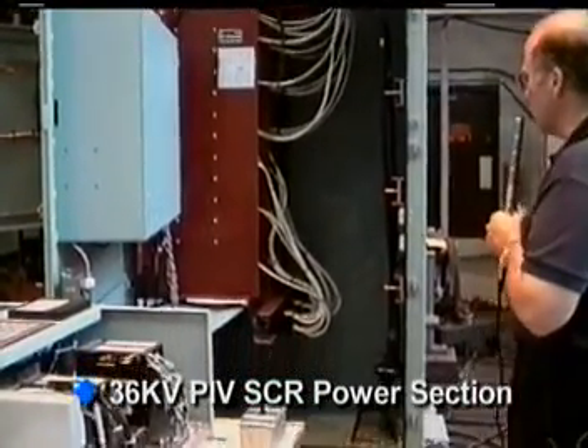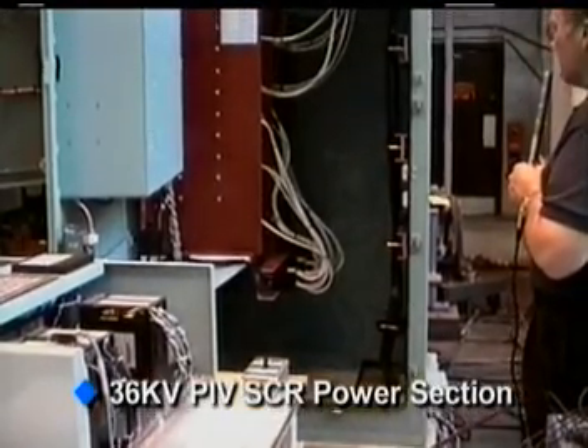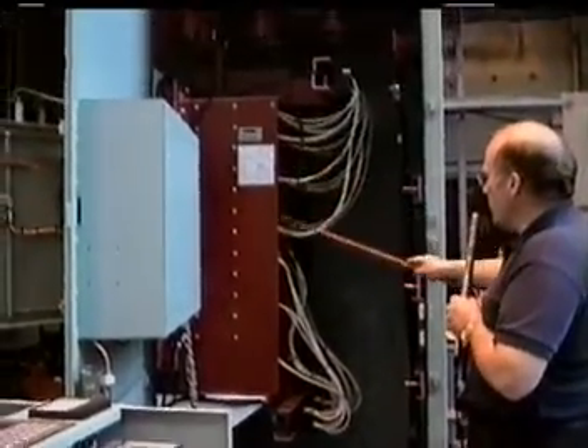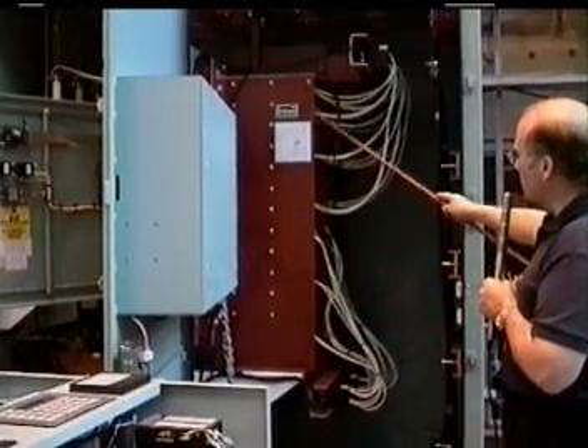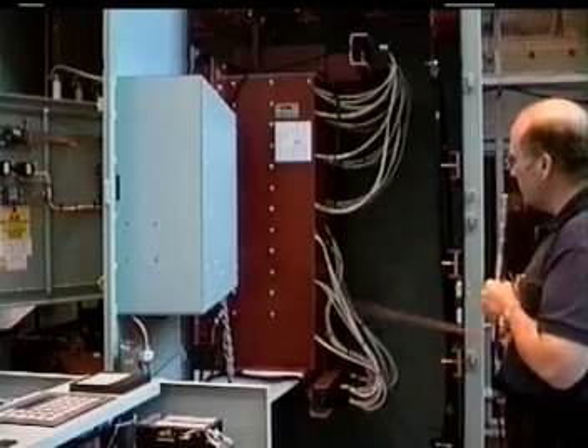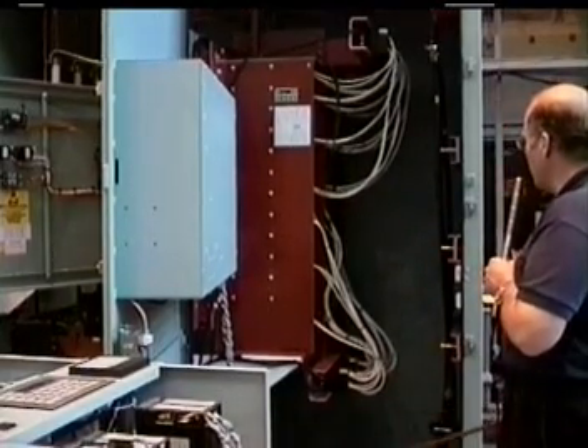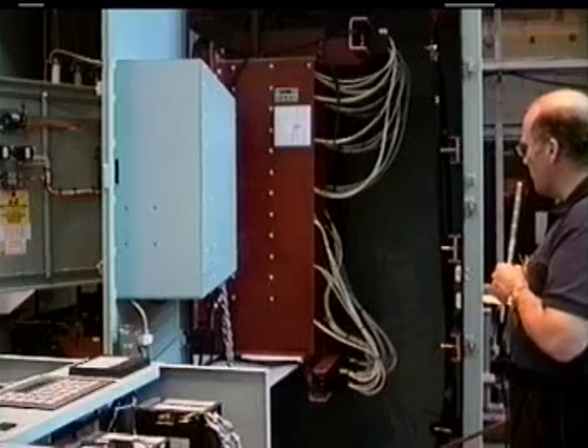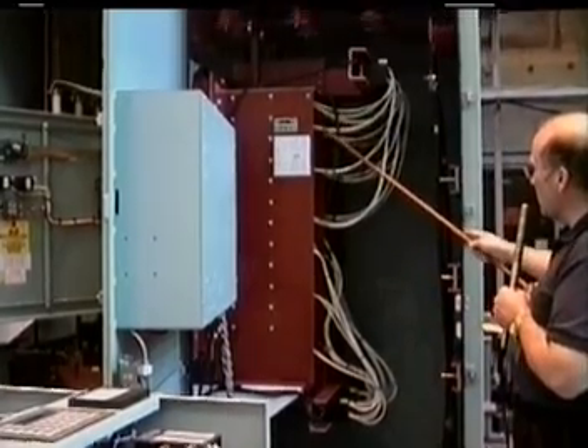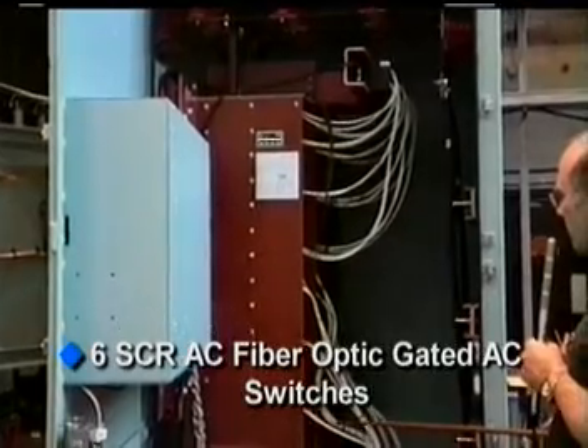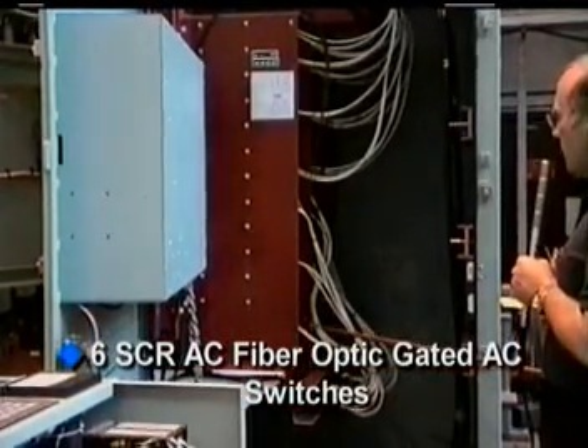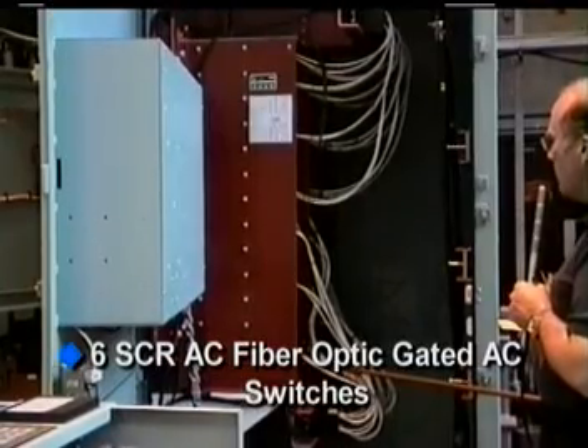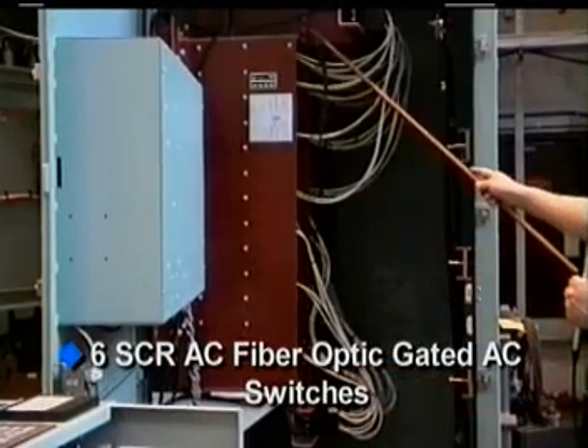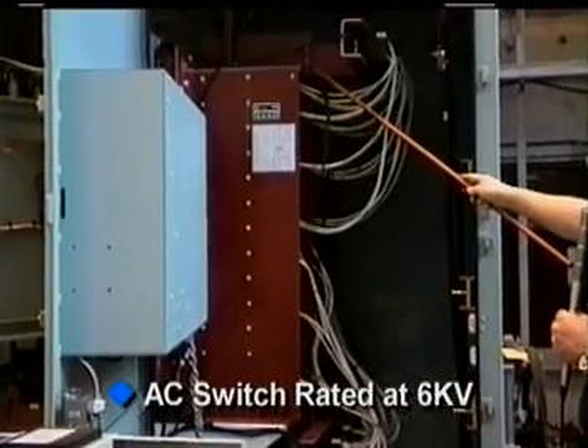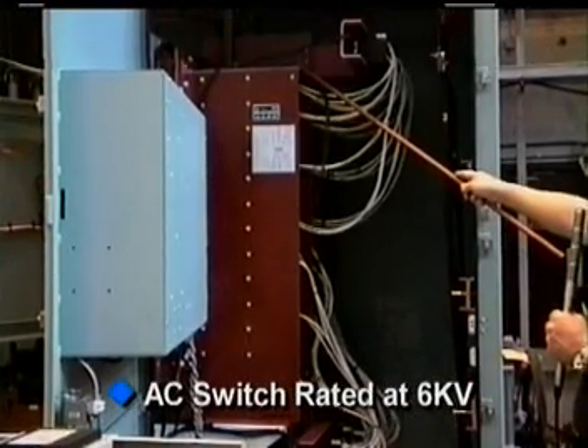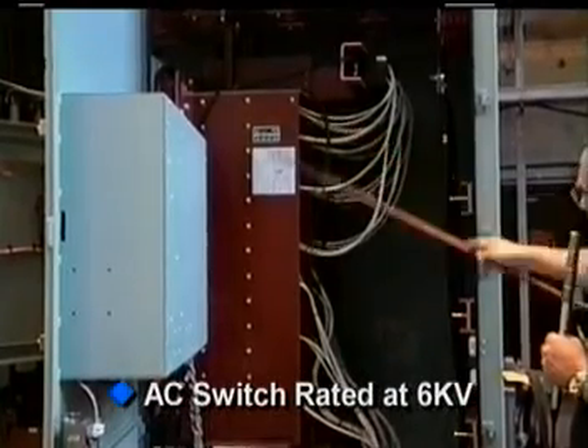In the starter enclosure is the SCR heatsink assemblies. The SCR heatsink assemblies are housed in a fiberglass enclosure within the starter section here, which is the final section of the entire combination starter. In here are 6 AC switches that we call cells that are configured as back-to-back SCRs to provide for variable voltage output. Each cell is rated 6 kV, so there's a total of 36 kV of isolation or peak inverse voltage rating from the top of the starter section here to the bottom.